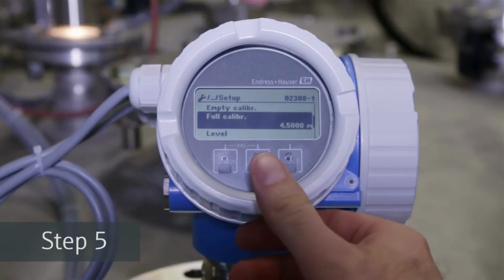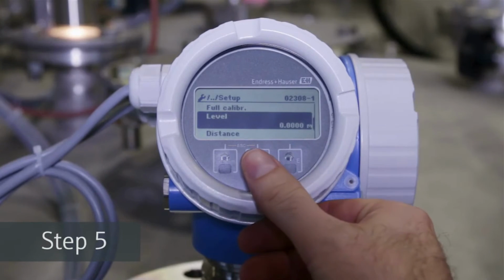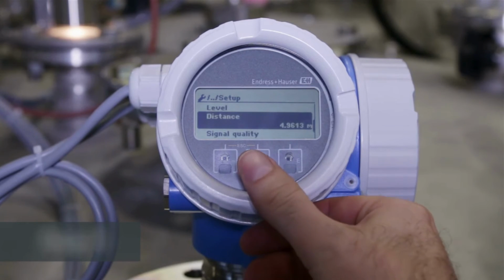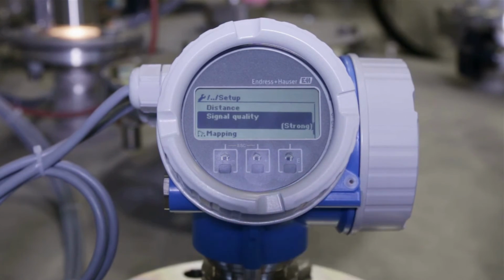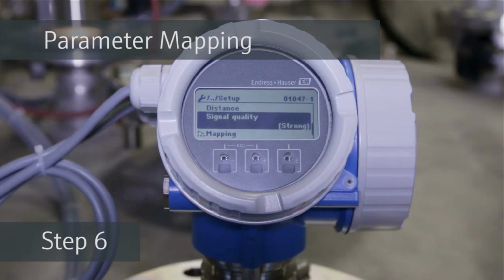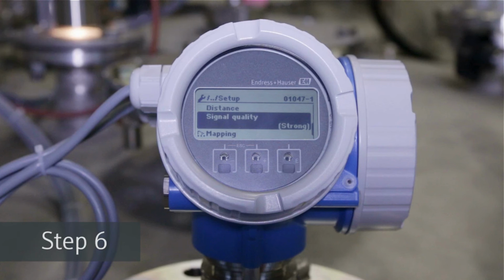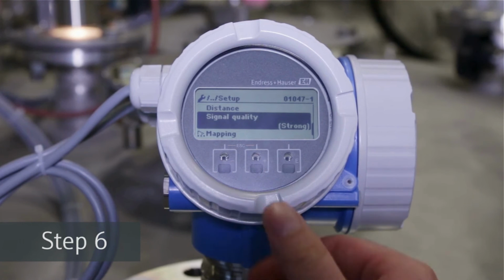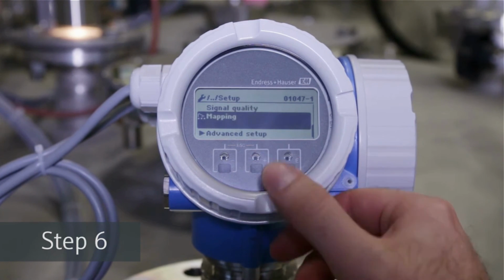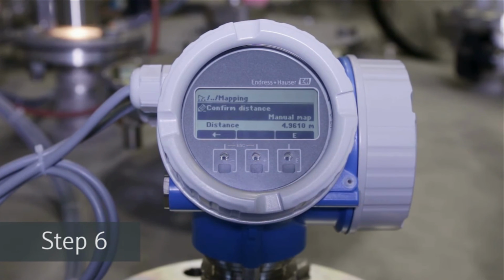The following three menu items assist you to access the currently measured level value, the distance, and the signal quality. To achieve the best possible measuring results, we recommend suppressing static interfering signals once, ideally with an empty tank. For this purpose, go to the mapping parameter and press the E key again.